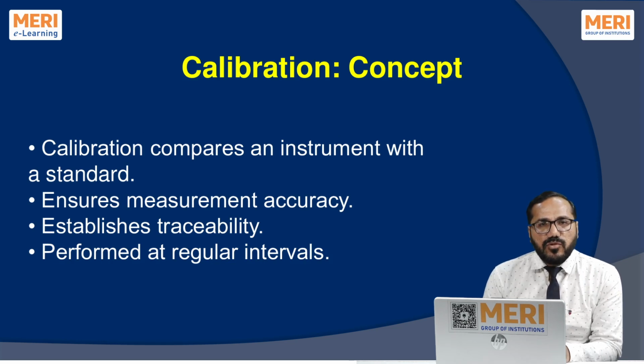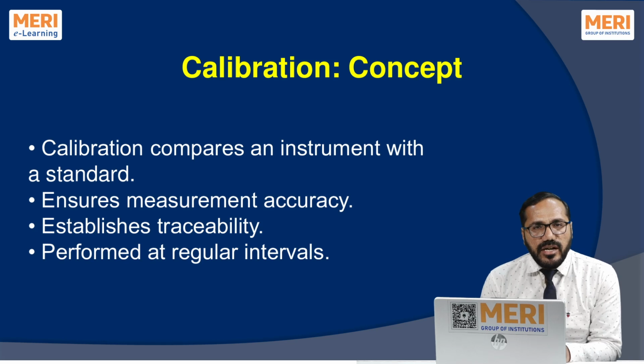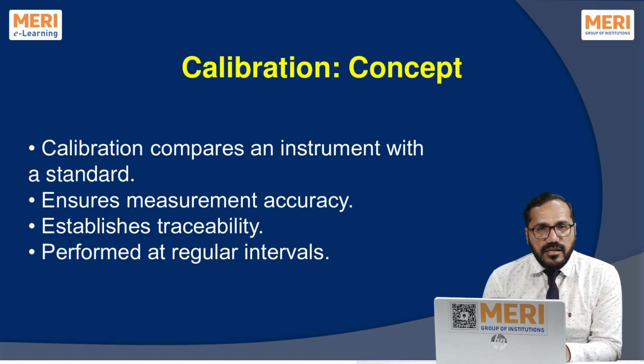Calibration concept. Calibration is the process of comparing a measurement instrument with a known and certified standard to verify the accuracy. The main purpose of calibration is to ensure that the instrument gives correct results within the specified limits. During calibration, the instrument is tested at different measurement points. The readings are compared with standard values. Any deviation is recorded. Correction factors may be applied. Calibration establishes traceability, meaning every measurement can be linked to national or international standards. Industries usually follow a calibration schedule, such as every 6 months or 1 year, depending on usage frequency. Proper calibration improves confidence in inspection results and ensures compliance with ISO 9001 and other quality standards.